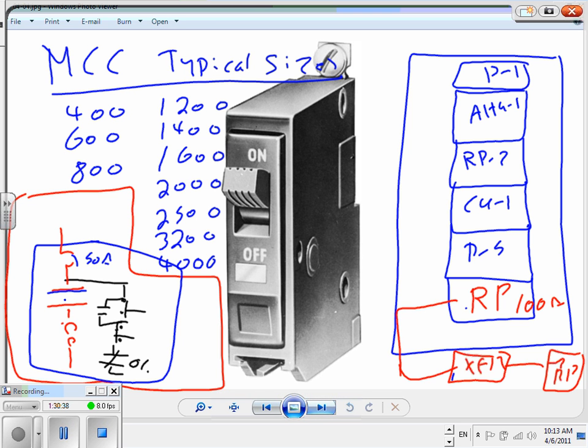If I have 5 cables coming to 1 circuit breaker, why would I do that? Parallel. If you're paralleling 5 conductors to carry 1600 amp, right? You're going to land them at the terminals of the circuit breaker. Here's 5, so you have to have 5 lugs, 5 cables, 1 lug per cable. So you can't put 2 cables under 1 lug unless it's rated for. Most of the time, guys, especially in this equipment, a lug per cable.